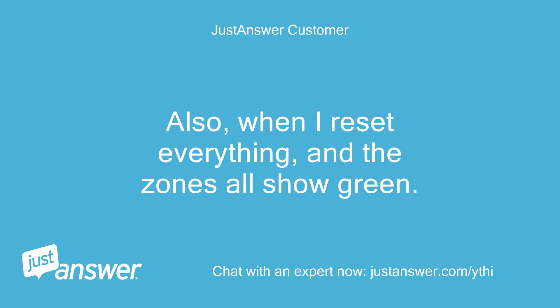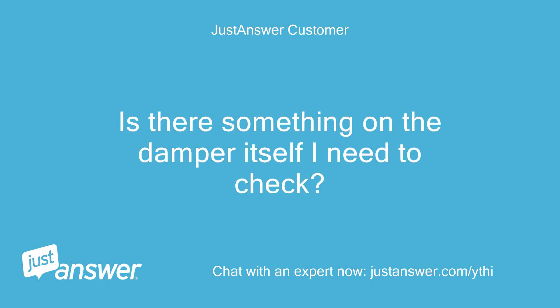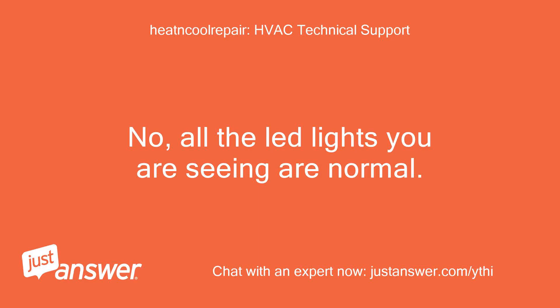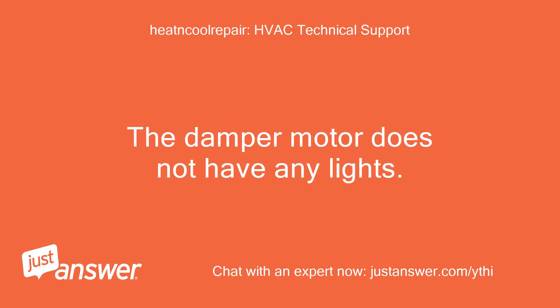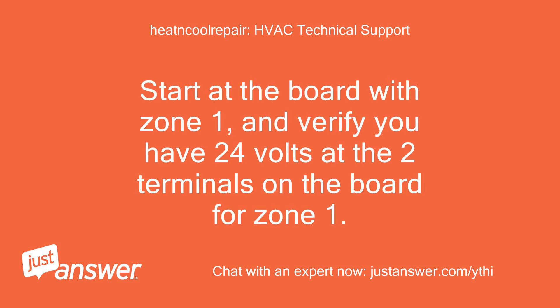When I reset everything and the zones all show green, when I turn on the thermostat the heat LED is red and the zone turns red too. Is there something on the damper itself I need to check? All the indicator lights you are seeing are normal. The damper motor does not have any lights. All you can check is the signal from the zone panel board to the zone motor. Start at the board with Zone 1 and verify you have 24 volts at the two terminals on the board for Zone 1.